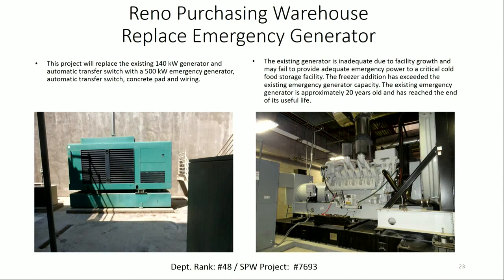Next at 48, the Reno Purchasing Warehouse. This project would replace the existing 140 kilowatt generator with a 500 kilowatt generator and a new transfer switch. Currently, the generator, despite being 20 years of age, is overloaded and cannot pick up and carry the third walk-in cooling box. So in the event of a power failure, the generator itself fails. It's just not large enough to carry the load.